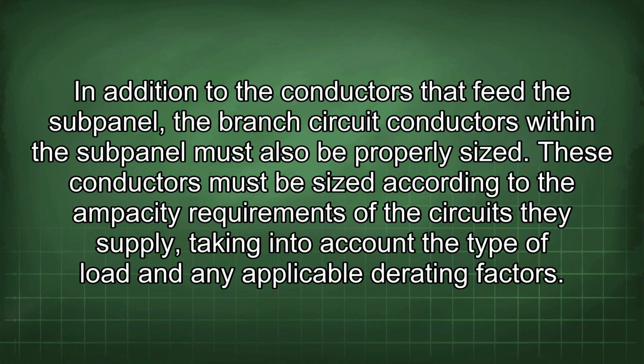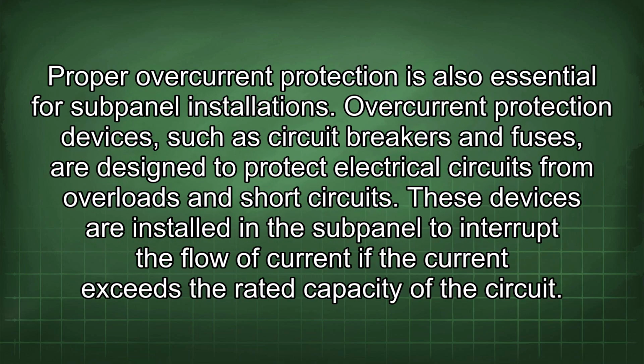In addition to the conductors that feed the subpanel, the branch circuit conductors within the subpanel must also be properly sized. These conductors must be sized according to the ampacity requirements of the circuits they supply, taking into account the type of load and any applicable derating factors. Proper overcurrent protection is also essential for subpanel installations. Overcurrent protection devices, such as circuit breakers and fuses, are designed to protect electrical circuits from overloads and short circuits.